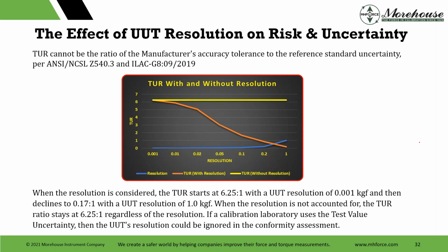The effect, TUR with and without resolution. If those are making measurements, TUR cannot be the ratio of the manufacturer's accuracy tolerance to the reference standard uncertainty. And this graph right here shows when the resolution is considered in our test uncertainty ratios. The TUR starts at 6.25 to 1 with a UUT resolution of 0.001 kgf and then declines as our resolution goes up. So we're not fooling anybody by doing this.